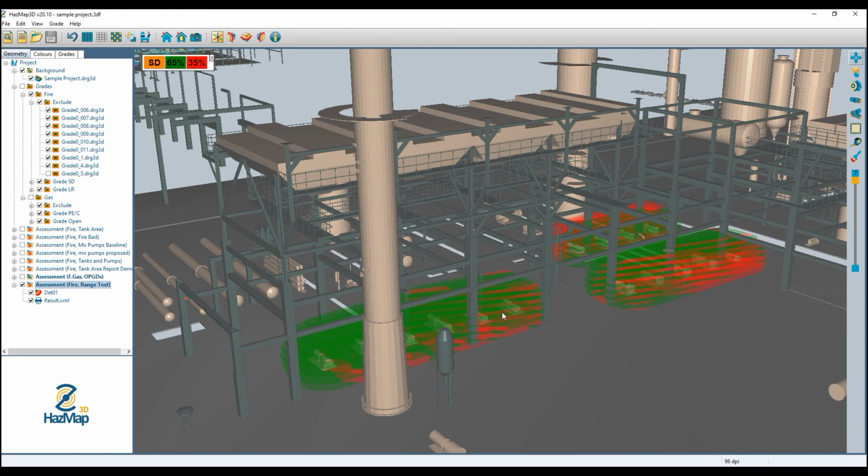an optimized system. If I want 2 out of N coverage for this space for a 500 kilowatt fire, I can probably do that with just 2 detectors, maybe 3. If I want good 2 out of N coverage for this with a 50 or 100 kilowatt fire, I'm probably going to need 4, 5, or 6 detectors to cover all of these pumps.